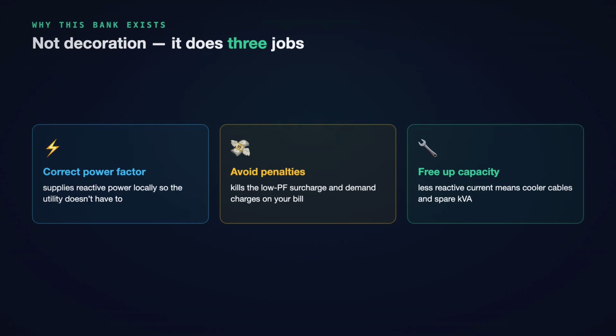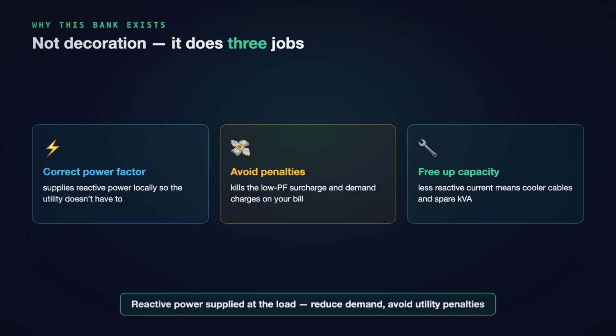It corrects your power factor up toward unity. It kills the low power factor surcharge and often the demand charge on your bill. And it frees up capacity. Less reactive current means cooler cables and spare kilovolt amps you can actually use. That is the promise of the capacitor bank single line diagram: reactive power supplied at the load on one readable page. So let us follow the power.